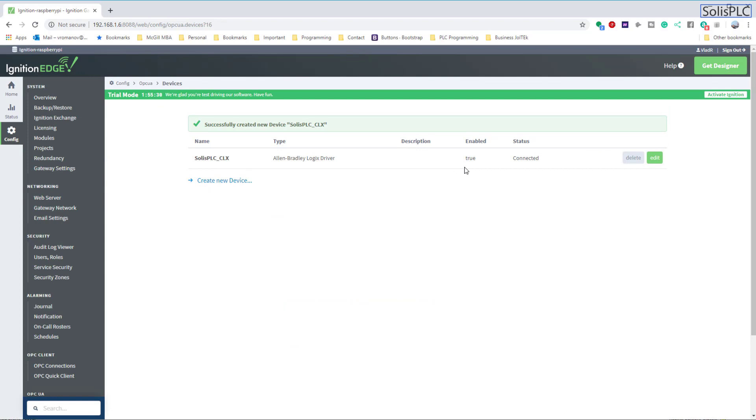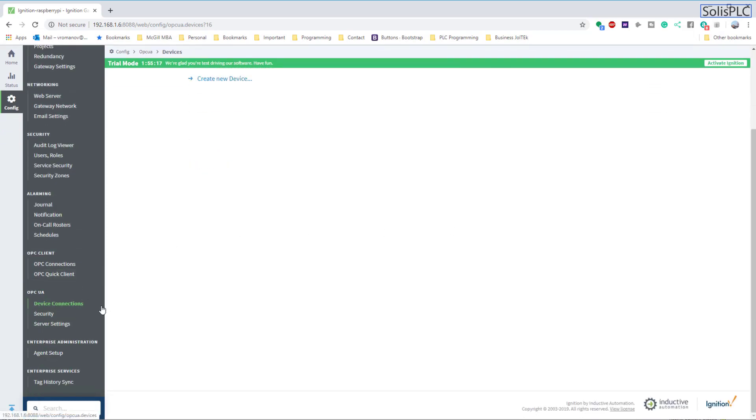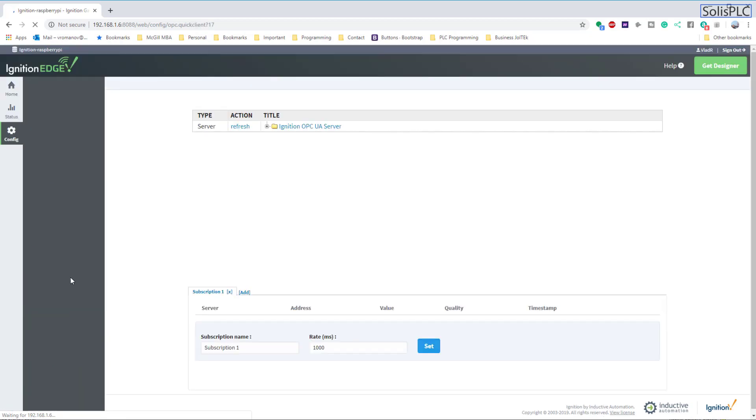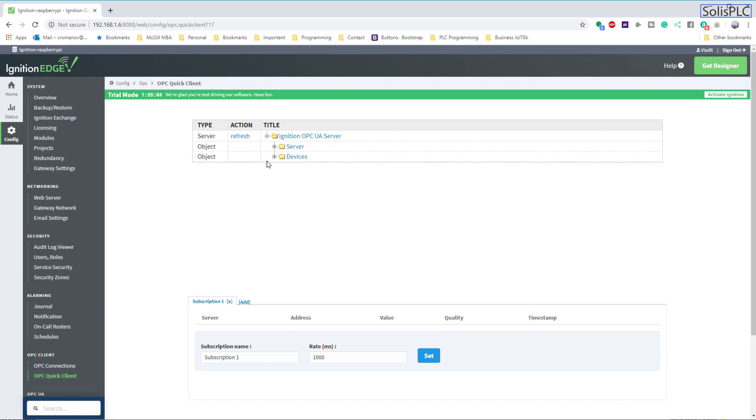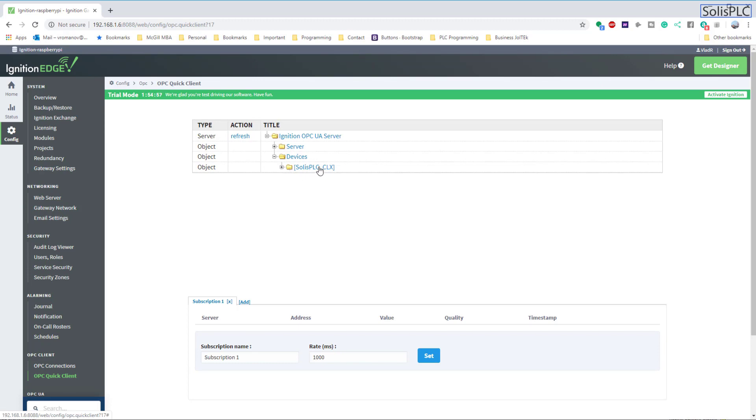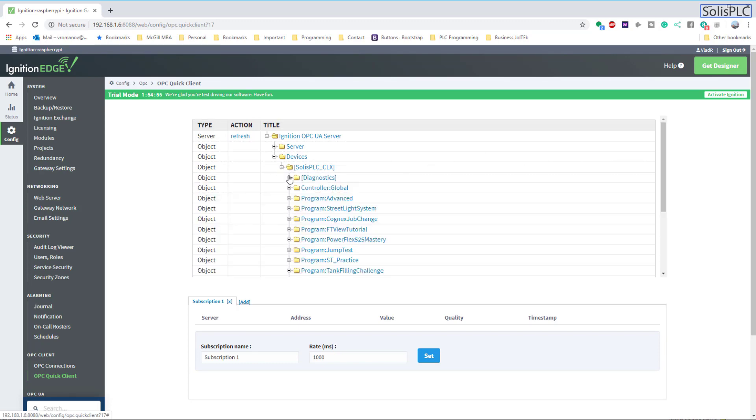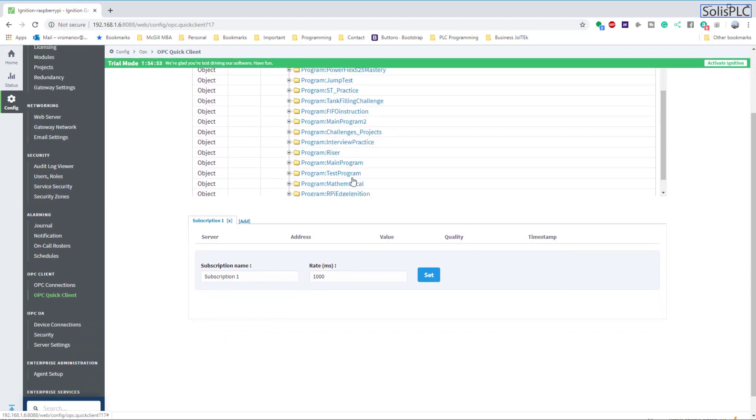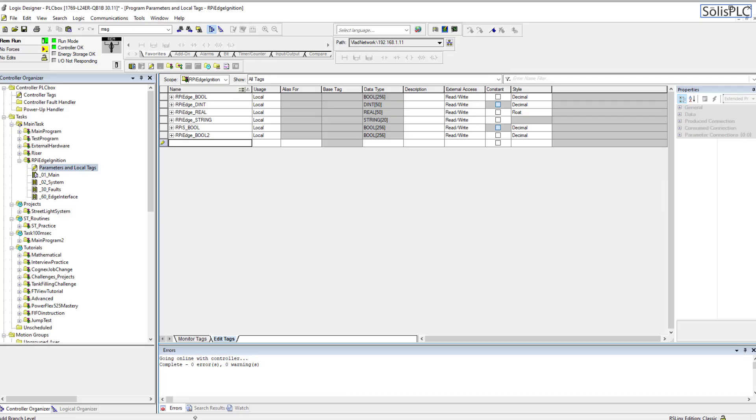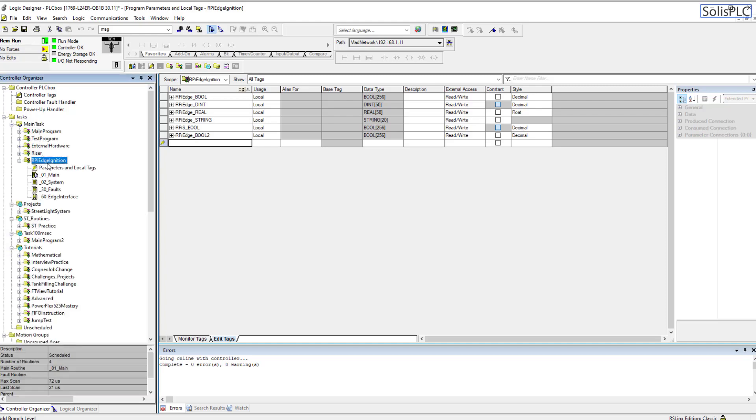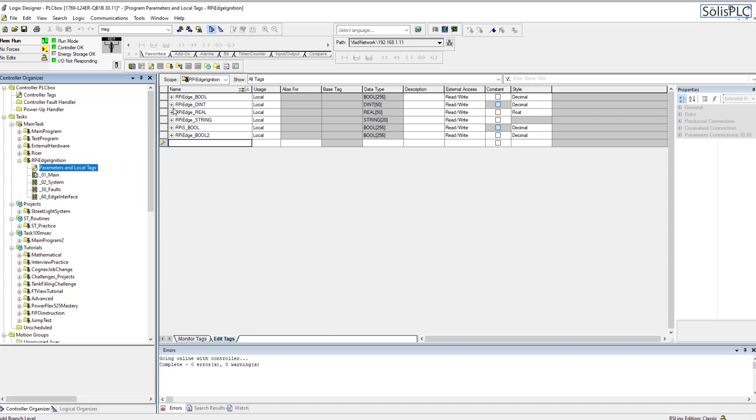And we have a PLC. We can see that its status is set to Connected because the Raspberry Pi or Ignition Edge is going to try and ping that PLC and make sure that it's what we've specified. Next thing that we do need to check, which is actually really handy, is this OPC Quick Client. So if we go into OPC, click Quick Client, we can look at the OPC UA server. Here if I expand these folders on their devices, you'll notice that we'll have our PLC listed here, and by browsing through here we can find the exact tag that we're looking for.